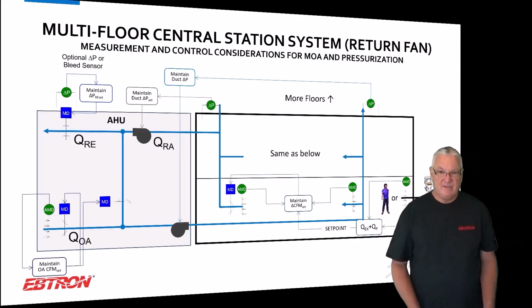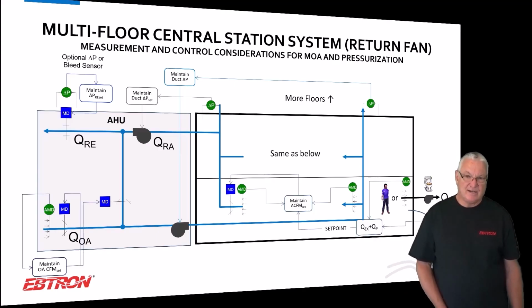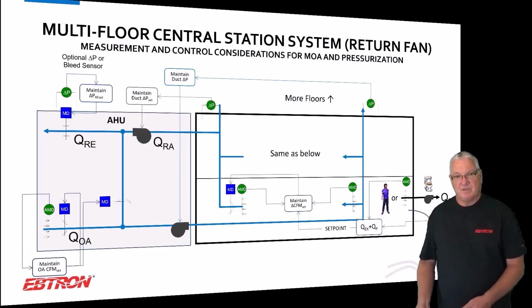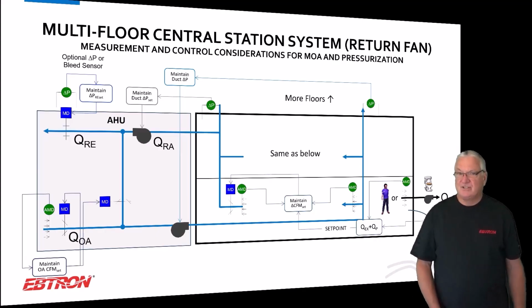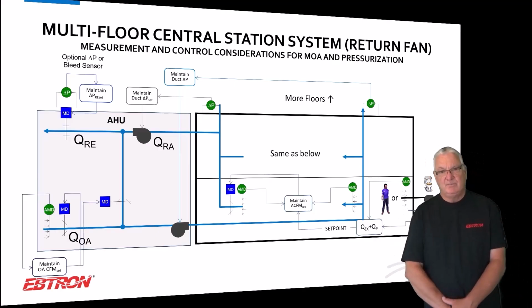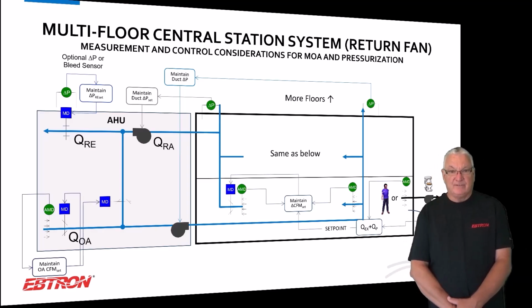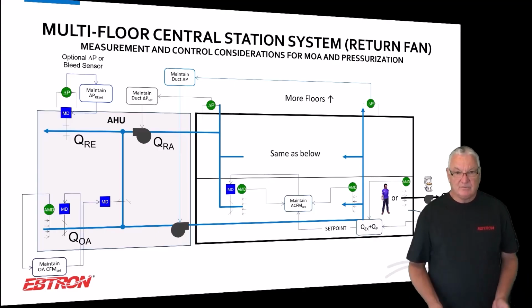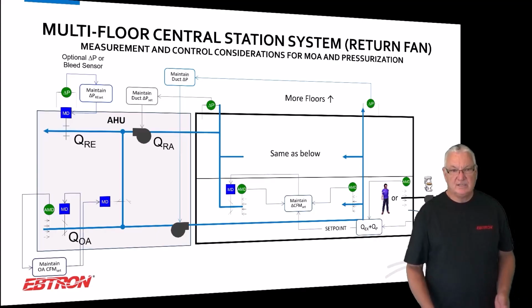Please don't sum up VAV boxes. Those flow measurement devices aren't accurate enough to use for tracking. Put a separate supply flow station in. We haven't gotten the products yet on the return side. If you're designing this from scratch, consider having some way to have a stub duct measurement of the returns. Maybe use our Air IQ package, which is a damper and a flow meter, to do that measurement. But if you just leave big chases going up the building on the return side, you're kind of destined to have pressurization problems. It's just a lot of change in pressure with elevation. It really is.